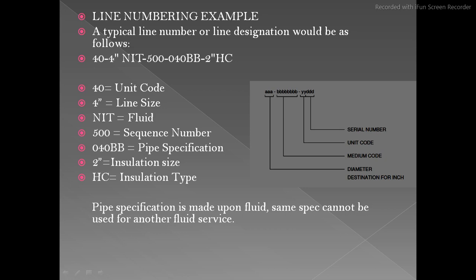From the legend sheet, you can see what each element stands for — serial number, unit code, medium code as fluid service, and the diameter in inches for pipe size. Most pipe specifications are made based on fluid service; the same spec cannot be used for another fluid service.